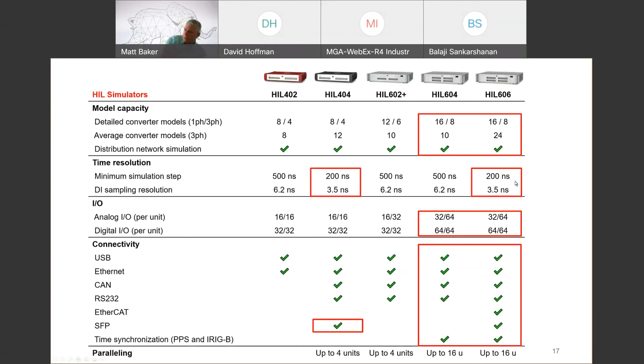They can run very fast for certain capability sets, like say one inverter, they can test one inverter. And they do some things better than Typhoon. They can handle thousands and thousands of nodes for transmission models that we're not really configured to work with. But if you want to put together a power electronic system with more than one inverter and associated digitally controlled protection, we can put together a huge solution and still run it at 400 nanoseconds, which is critically important because of that timing I've already described.